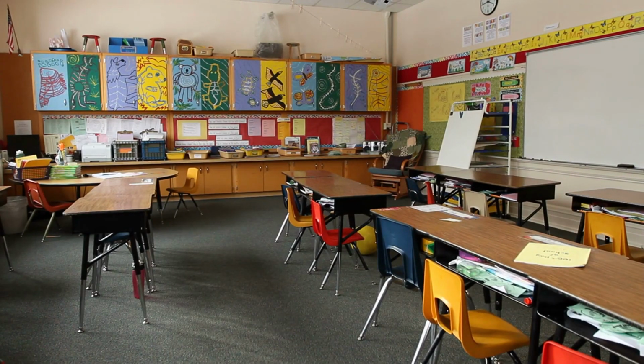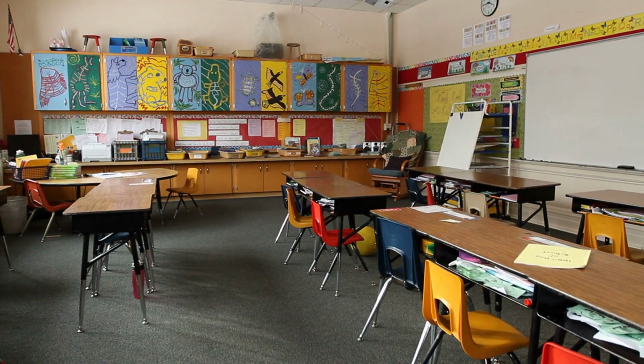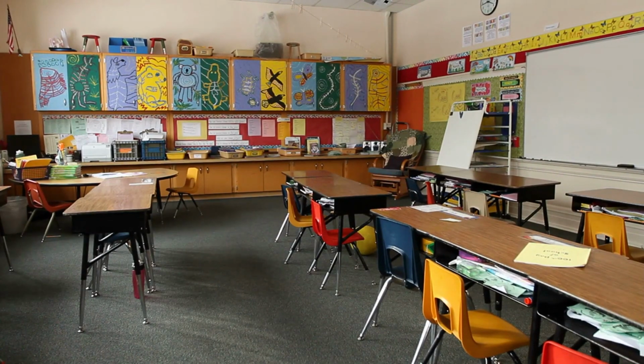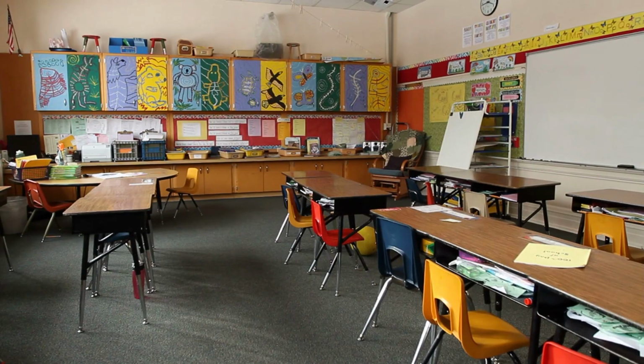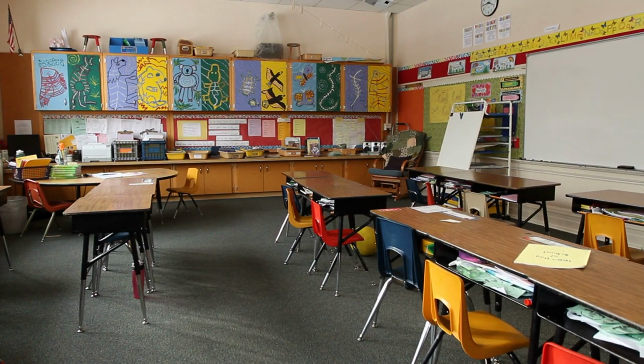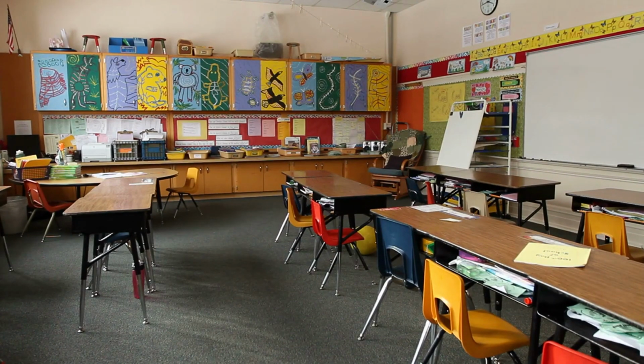VAV boxes. 6. Each classroom and office must have a non-fan powered VAV box with integral sound attenuator. 7. Under low load, boxes throttle down supply air. 8. Acoustical lining downstream is allowed only per DR 6.2.25, acoustical standards, special classrooms, pre-K to 2nd grade. 9. Classrooms with adjoining toilets may exhaust part of their outside air through the toilet exhaust fan.